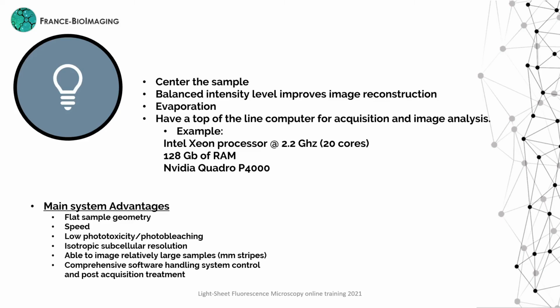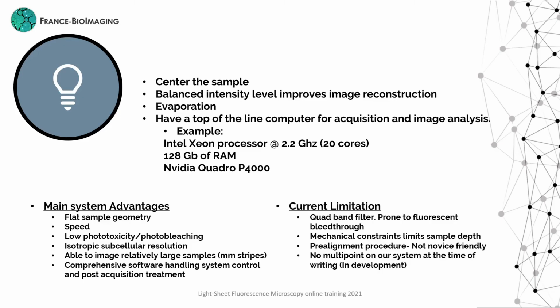In summary, DiSPIM is an interesting system if you plan to work on flat sample geometry. As with all light sheet microscopes, you can expect fast acquisition and low phototoxicity. Post-processing allows subcellular resolution on relatively large samples. However, for some applications, having quad band filters may become an issue if you have fluorescent crosstalk. You need to be aware of the depth that you can reach with the objectives due to mechanical constraints.